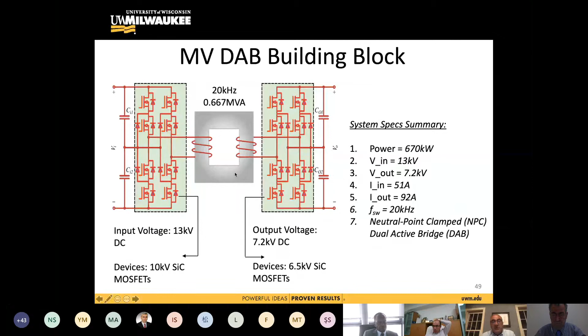So one of the big tasks is really the design of the transformer, which is really complex. However, before that, one of the big cases that we have is the medium voltage. When you have high voltage in a system, like this DAB case here, this is the transformer primary and this is the secondary. You have to identify all the voltage differences and how you are going to insulate different parts of the system, and what the insulation levels are. If you don't ground the core, the insulation can be at 6.5 kV. And if you ground it, then you have to move it up to 13.8 kV for the 13 kV system.